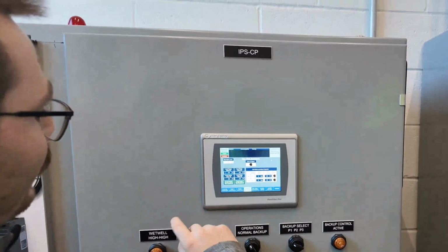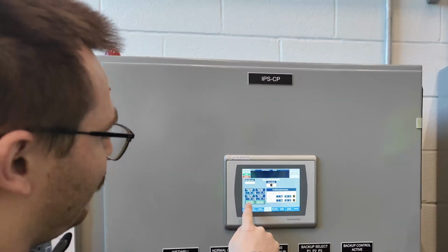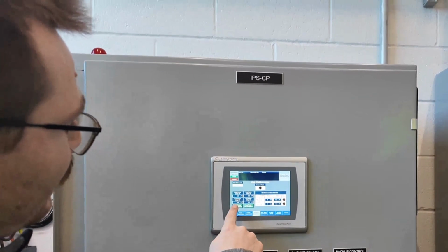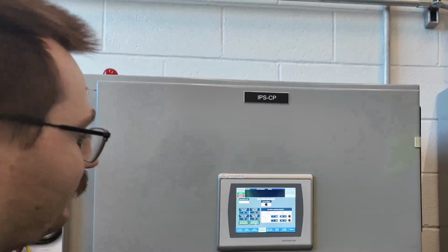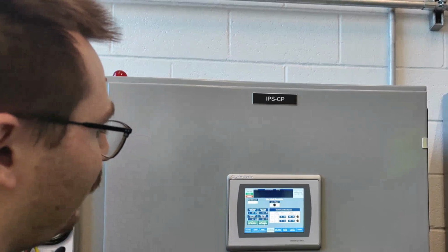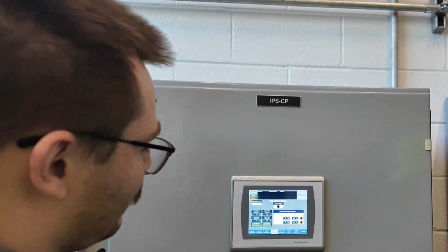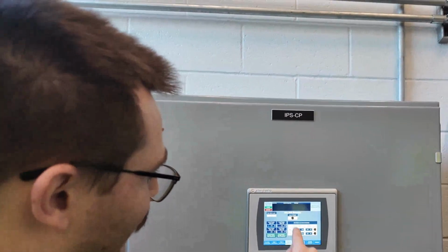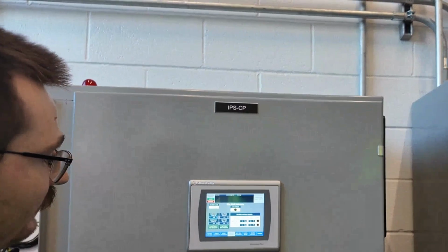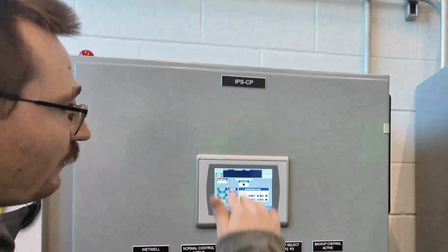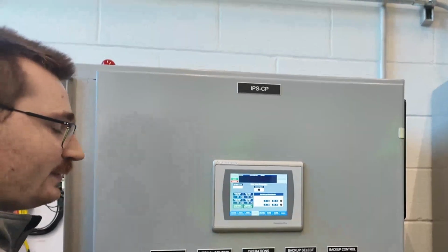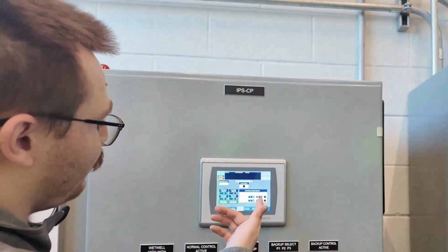And then if the lead pump or the lag pump is called to run, there's going to be a visual indication down here. It's going to light up and say lag pump required or lead pump required. And then we also have a signal loss. So if you ever lose your well level signal, you have a visual display right up here. It's going to tell you the transducer is reading over range or under range, and that there could be an issue with it.